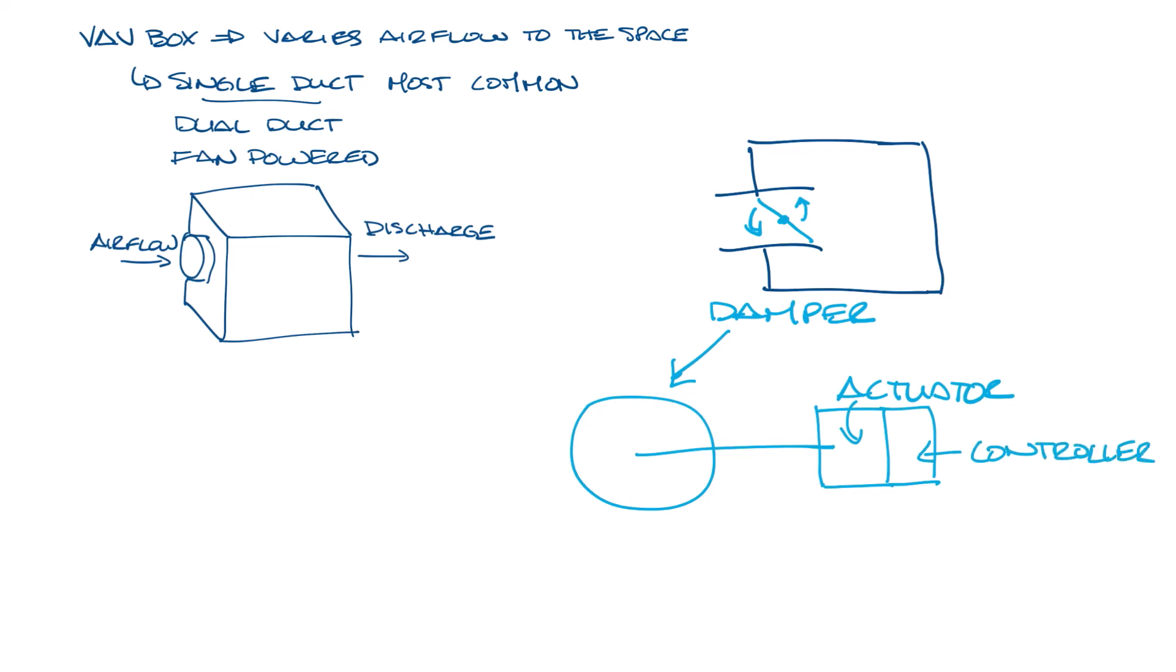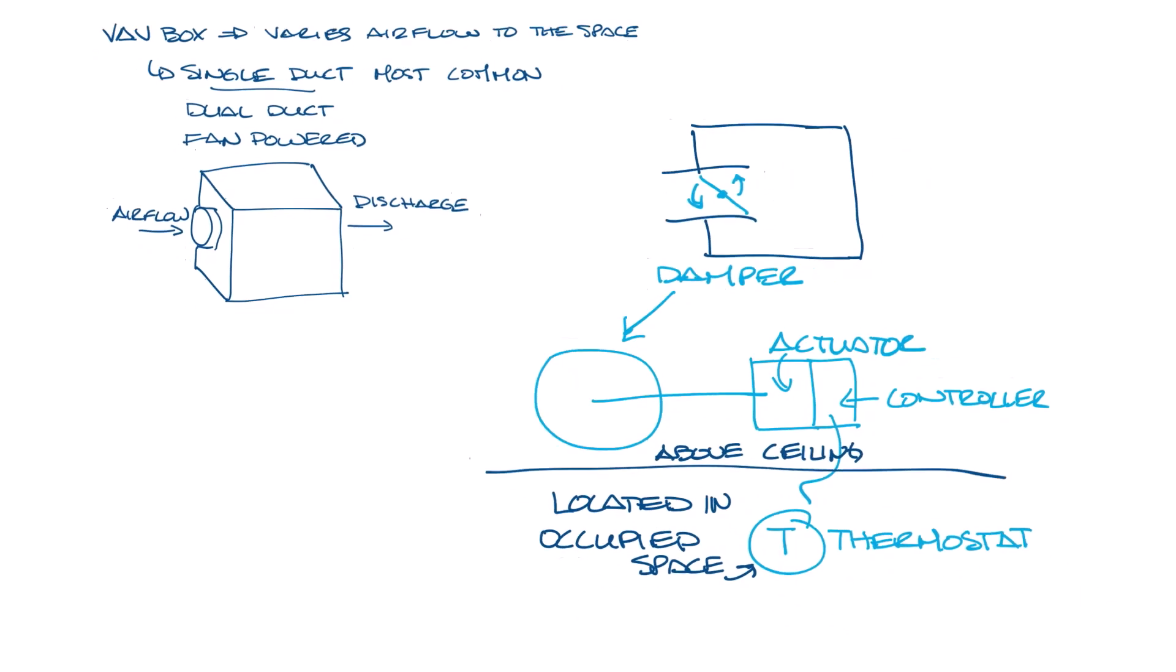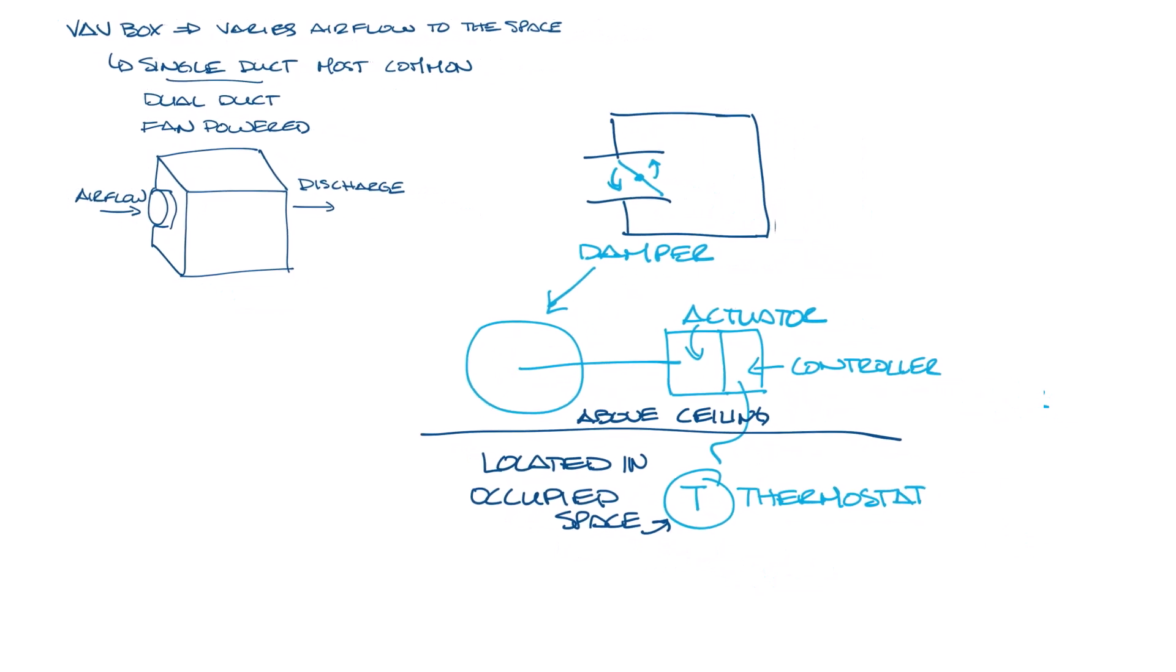Most controllers today are digital or DDC controls, although you'll see some analog and pneumatic still around. Connected to the controller is a thermostat that would be located on the wall in the space where the VAV box is supplying. VAV boxes will usually control a zone made up of several offices or spaces. So let's draw a line here. All of this is above the ceiling and the thermostat's in the space. All these components work together to maintain the temperature that the thermostat is set to.